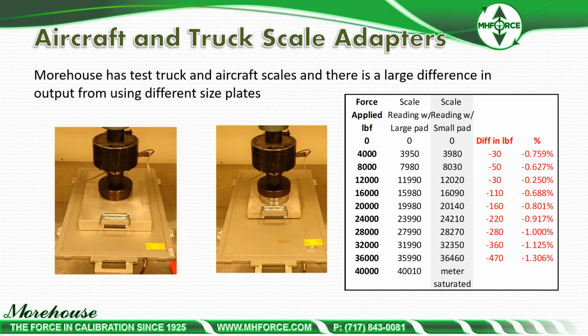At 40,000 pounds with the large pad, the one scale reads okay, real close, 40,010, whereas on the other end with the small pad, the meter saturates. At 36,000, we have a 1.30% error. That's very, very large for what we're talking about. It's way over the specification limit of this particular one. And if you had varying size truck scales or varying size footprints, this scale is all over the place and probably does not have what is needed to standardize that measurement.